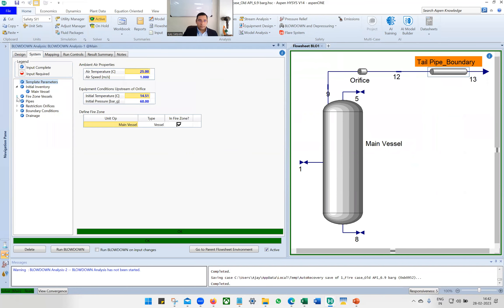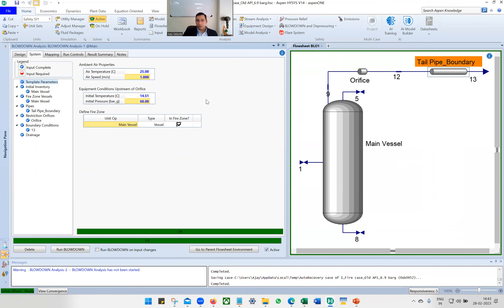Then go to System. In the template parameters, fill in air temperature and air speed. For initial temperature, use maximum operating temperature. For initial pressure, since it is a fire case depressurization, we start with the design pressure or PSV set pressure — in this case 60 bar gauge. Check the fire zone box.